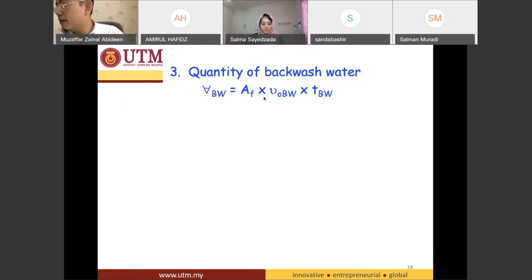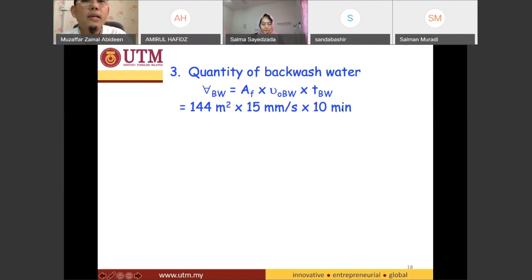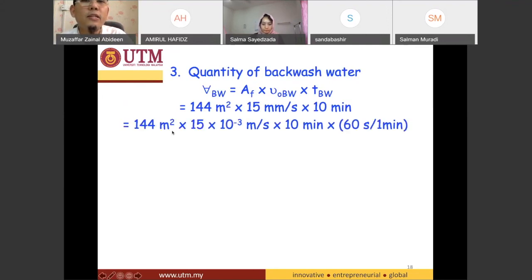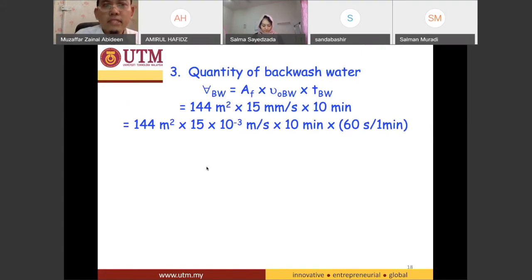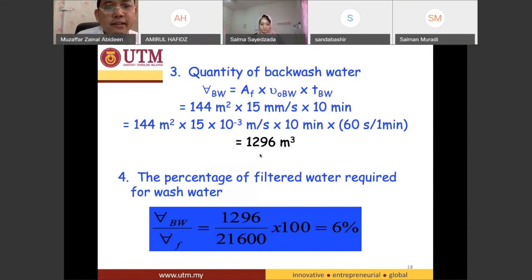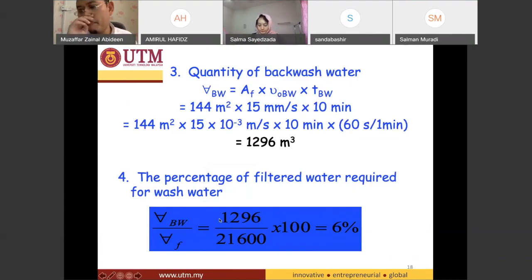The backwash rate is 15 millimeters per second and the time for backwash is only 10 minutes in one day. Plugging in all the numbers, the volume of backwash works out to 1,296 meter cubed. Therefore, the percentage is 1,296 divided by 21,600 times 100, which equals 6%. So 6% is the percentage of water that needs to be kept for backwash purposes.